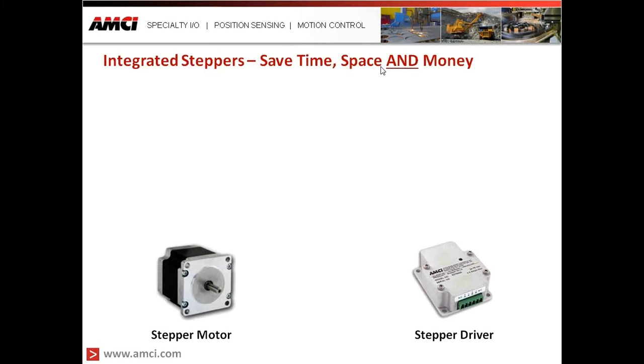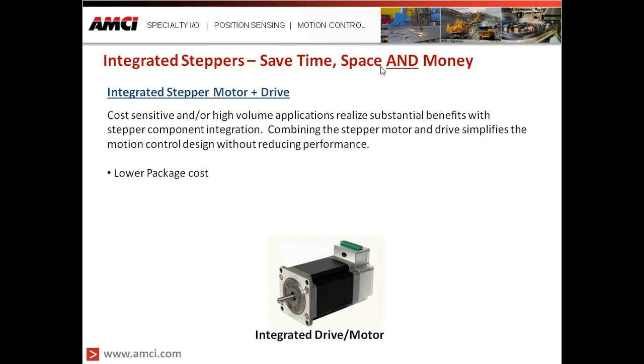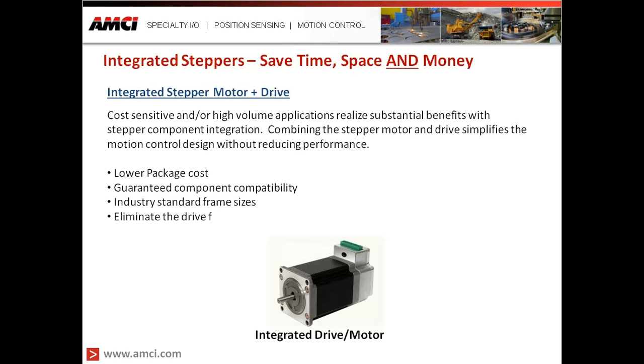The first package is the integrated drive and motor. Cost-sensitive and high-volume applications realize substantial benefits when stepper components are integrated. Combining the stepper motor and drive simplifies the motion control design without reducing performance. It lowers package costs, guarantees component compatibility between the drive and motor, uses industry-standard motor frame sizes — typically NEMA 23 or NEMA 17 — eliminates the drive from the panel saving panel space, and uses standard PLC PTO output for control.